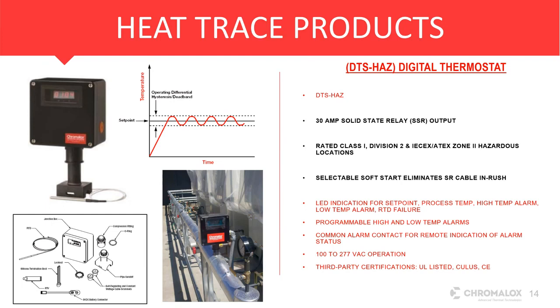So it's your power connection kit, your sensor, and your single line controller all in one box. What that provides to you is an integral soft start. It basically will pulse on your cable. There's no programming, there's nothing else you need to do besides set it and forget it. But this will allow you to have longer runs of cable and eliminate the concern of tripping on cold starts. Like I said, it has a pulse mechanism in there that acts as an integral soft start.